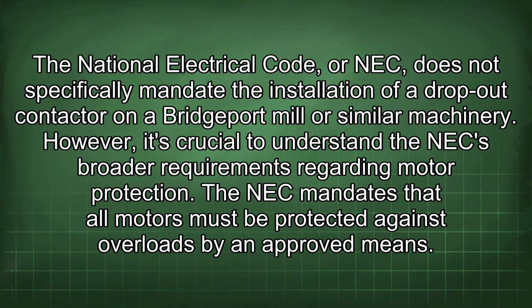The National Electrical Code, or NEC, does not specifically mandate the installation of a dropout contactor on a Bridgeport mill or similar machinery. However, it is crucial to understand the NEC's broader requirements regarding motor protection. The NEC mandates that all motors must be protected against overloads by an approved means.